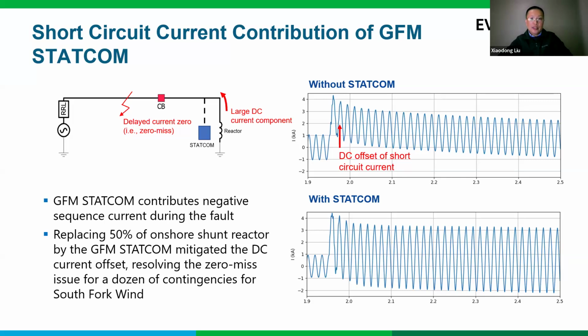Then the project modified the design and replaced 50% of the reactor with the STATCOM and resolved the zero miss issue, because the STATCOM contributes AC short circuit current and does not generate a DC current component. From this point of view, the STATCOM is even better than the SynCon. From the diagram right here, you can see that the installation of the STATCOM increases the short circuit current, and the short circuit current crosses zero within multiple cycles of the fault, right? Which means the line breaker can safely interrupt the fault and resolve the zero miss issue.